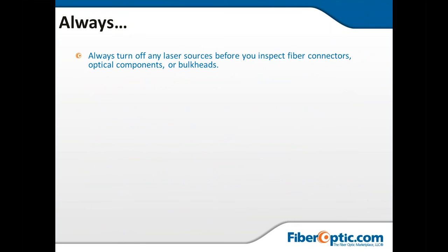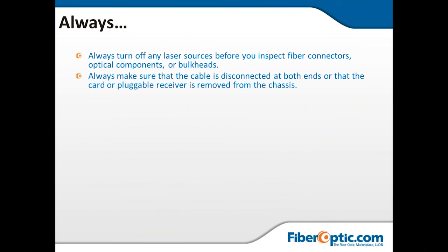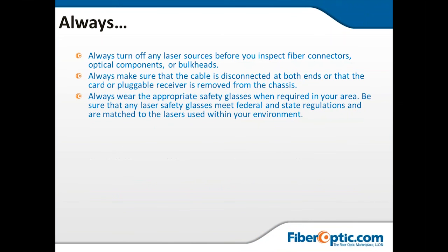Here's some safety stuff: make sure the laser's off. Always make sure the cable is disconnected on both ends, or pluggable receivers removed, because you don't want the laser transmitting when you're cleaning, it can send a back reflection and damage your equipment. Wear your safety glasses, that's great, can't hurt. If you're working around laser radiation, make sure you have approved safety glasses.